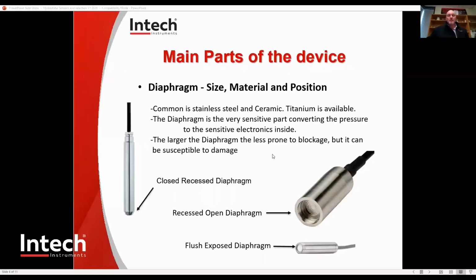You can see here, as you see, common is stainless steel and ceramic. Titanium is available. The diaphragm is very sensitive. The larger diaphragm is less prone to blockage. You can see here, you've got a closed recessed diaphragm. Here we have a recessed diaphragm, and it is open, so you can actually see the diaphragm in there, and the bottom there. And the one I've shown you is a flush exposed diaphragm.